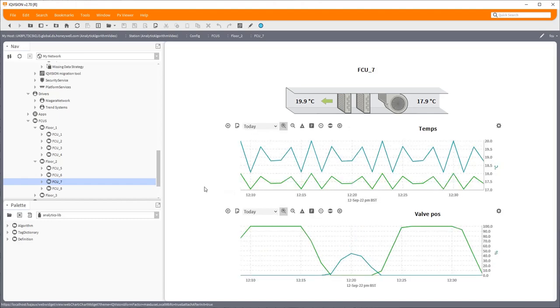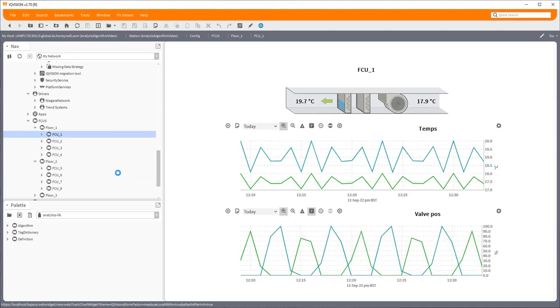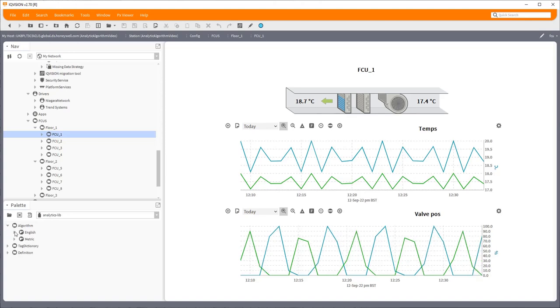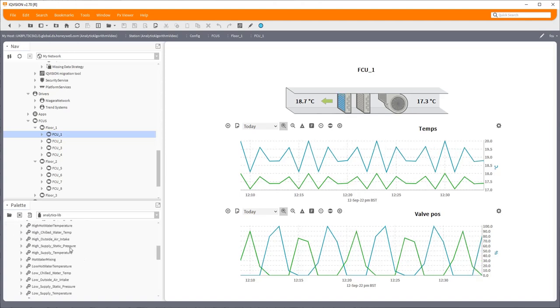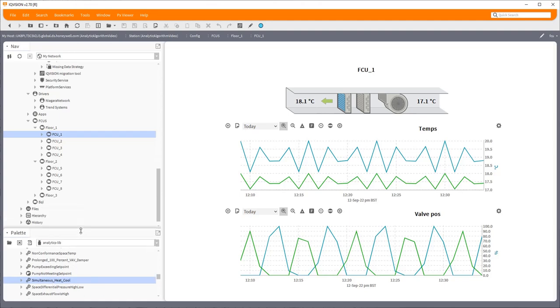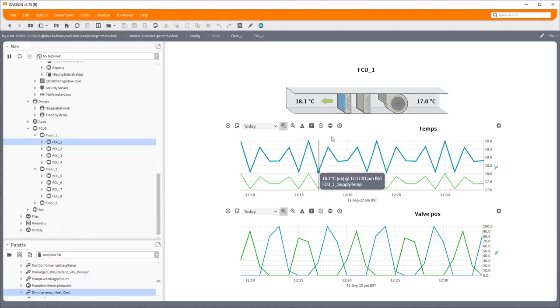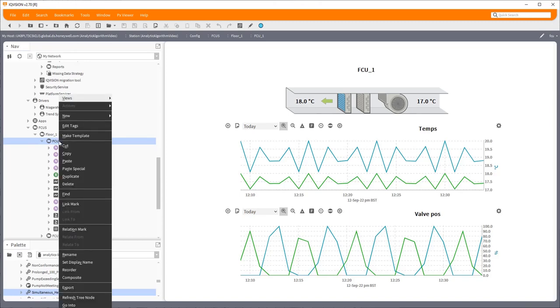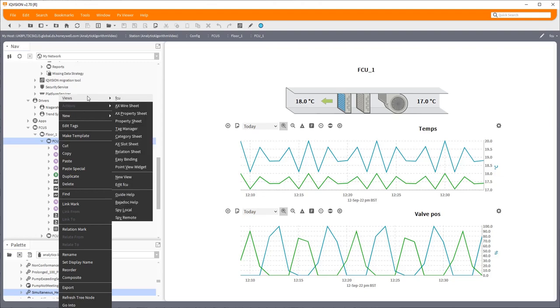Now the analytic I'm going to put in today will look for heating and cooling coils both open by more than 10 percent simultaneously. Quite a simple one. There's a few other examples we could put in there, and in fact this particular example is one of the ones which is in the library already. If you open the palette analytics library you will see there's a simultaneous heating and cooling algorithm already in there, although it's much more complicated than what I'm about to show you because I'm going to keep this nice and simple.